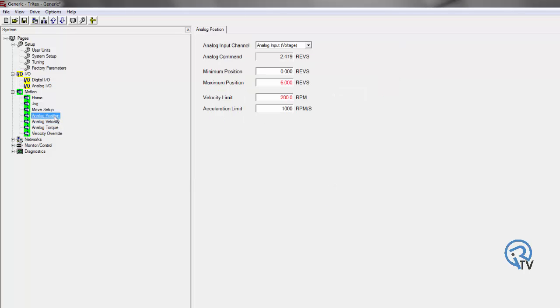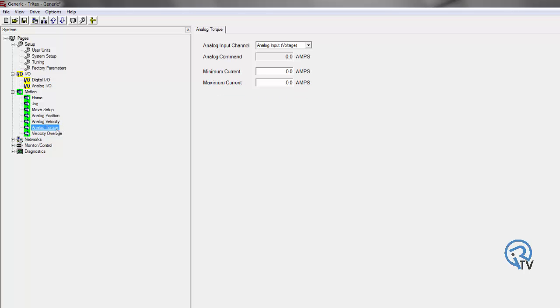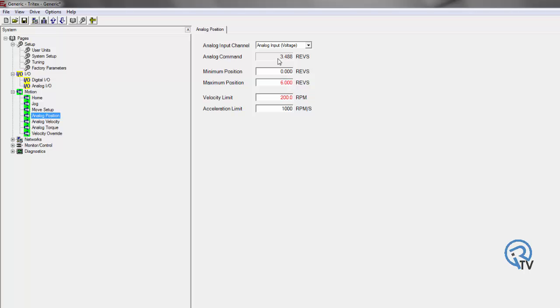I can do an analog to position, analog to velocity, or analog torque. So based off my analog to position, I can say at a certain analog command, I'm going to go to a certain position.